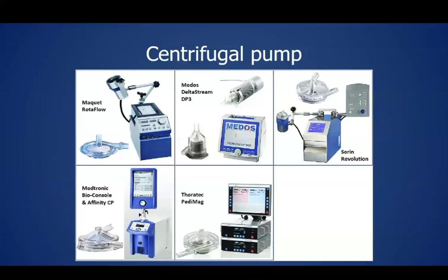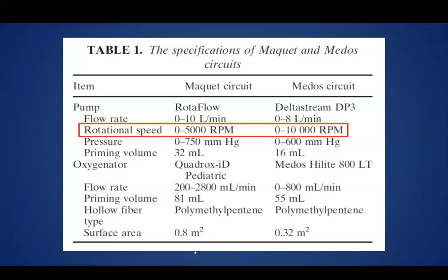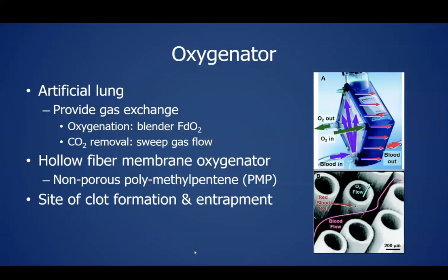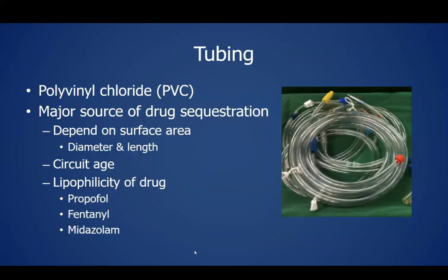Example of different pump heads for an ECMO. Of note, the Medos pump has a max speed of 10,000 RPM, while the others have a max of 5,000 RPM. The oxygenator provides gas exchange for blood, and it is the main site of clot formation. CO2 removal can be adjusted with the sweep gas flow rate. FDO2 stands for fraction of delivered oxygen applied to the oxygenator. These are the different oxygenator models. The circuit tubing, made of PVC, is the major site of lipophilic drug sequestration, so a higher dose is required for the majority of sedative drugs such as propofol, fentanyl, and midazolam.